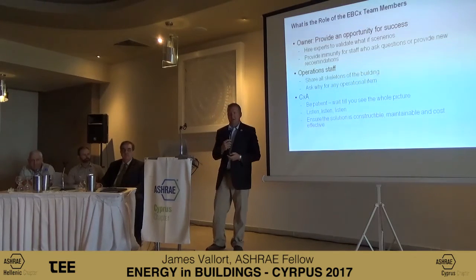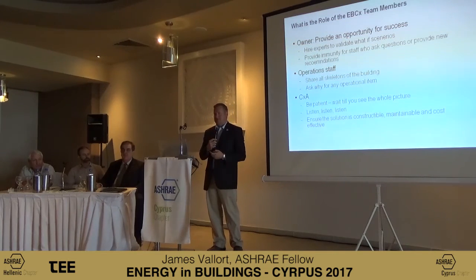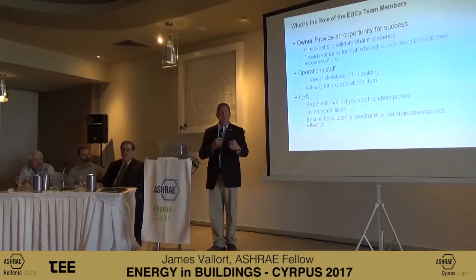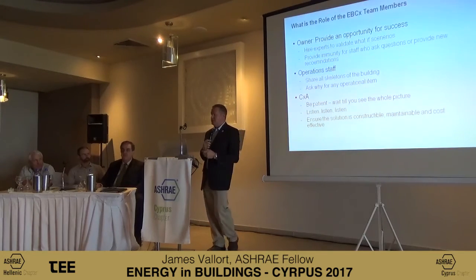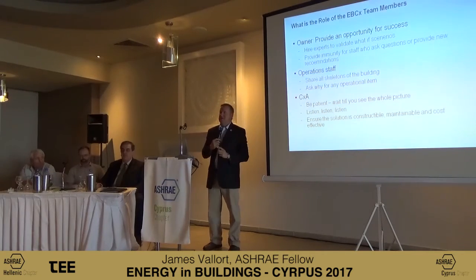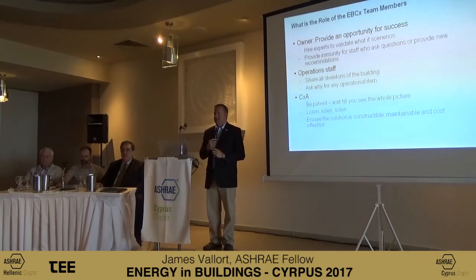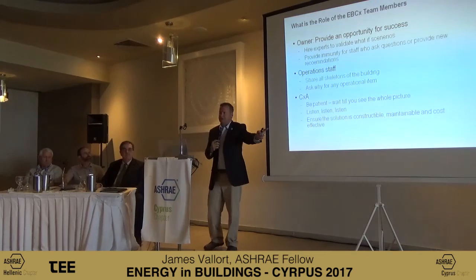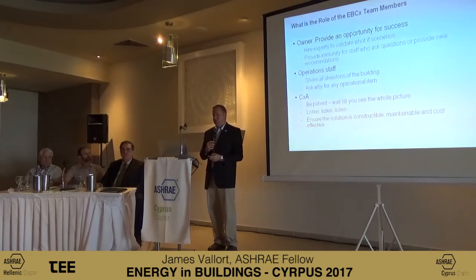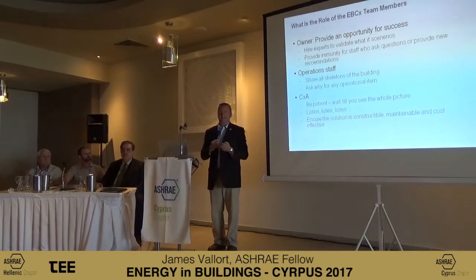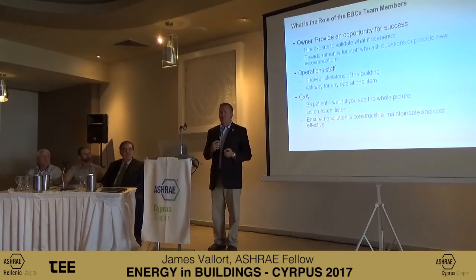When doing commissioning, consider the roles of people. The operations staff are your most valuable resource — they'll tell you all the skeletons in the closet. They might not know why, but ask what can be done differently and they'll point out problems. Listen to what the problem is, because you might have a different solution — it may be one or two layers deep in the onion. As the engineer helping with commissioning, be patient and listen. Don't just jump to the first conclusion. Many issues that appear to be chiller inefficiency may actually be due to a pumping system in one of the buildings, not the chiller itself.